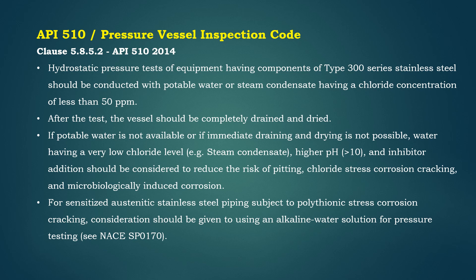For microbiologically induced corrosion, and for sensitized austenitic stainless steel piping subject to polythionic stress corrosion cracking, consideration should be given to using an alkaline water solution for pressure testing.